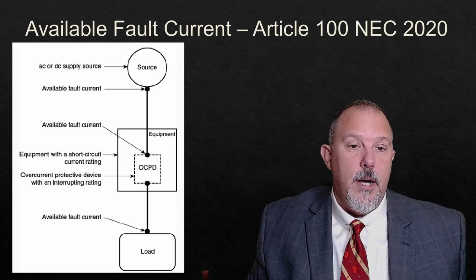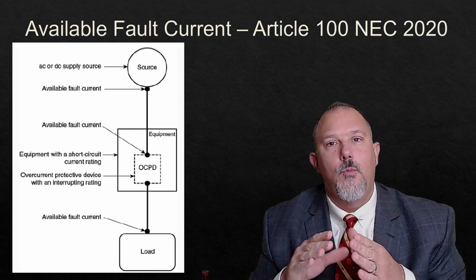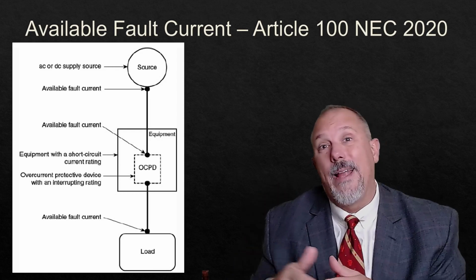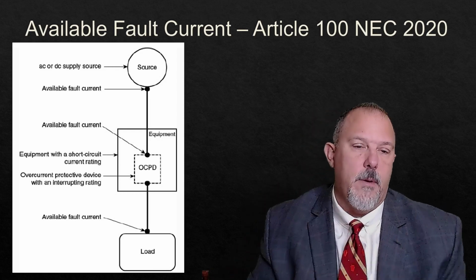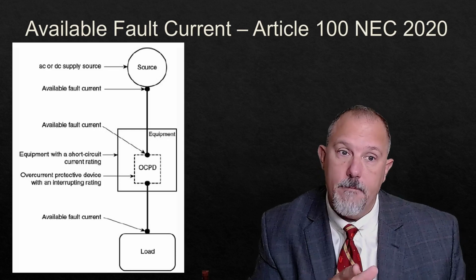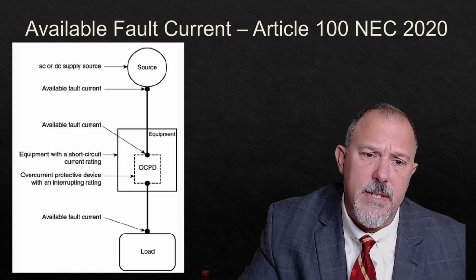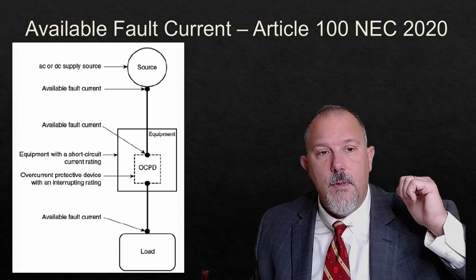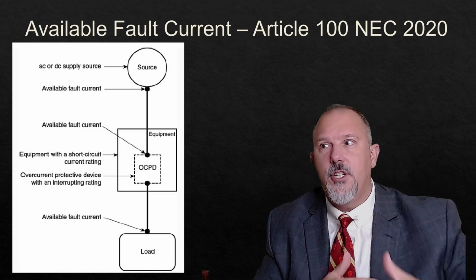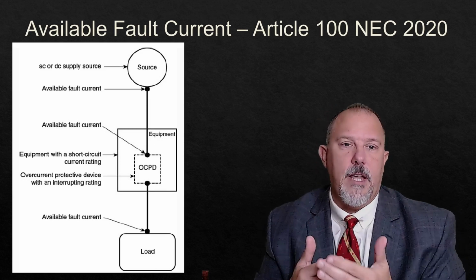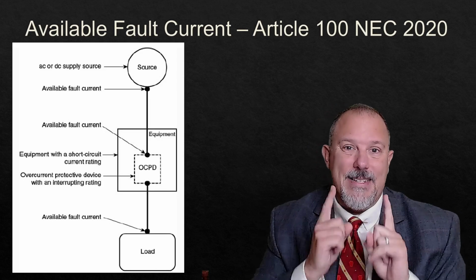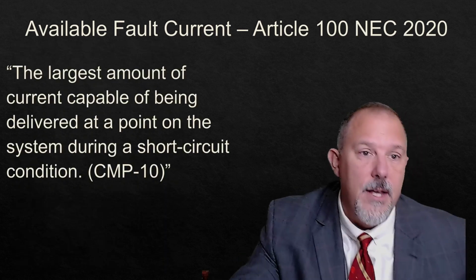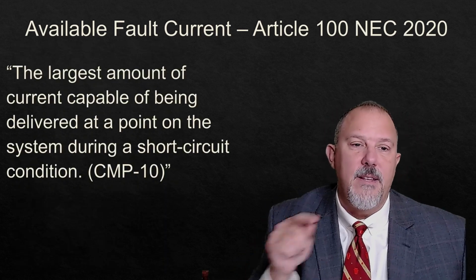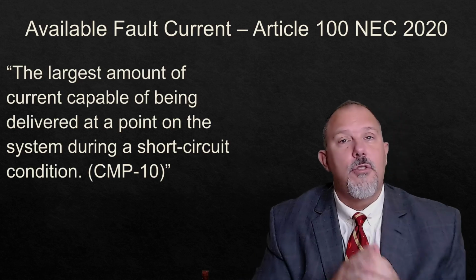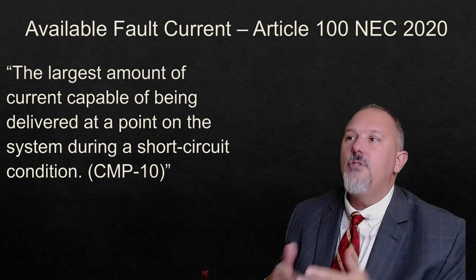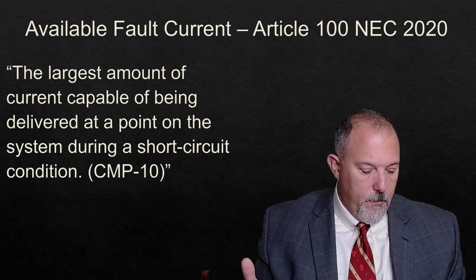So why do we do that? Because you want the maximum available fault current. You don't want to go downstream. You want to be at that equipment, and that will tell you the interrupting rating. Short circuit current rating is very similar. So the changes in the 2020 cycle were basically looking at, they wanted to create a term. Now remember what the definition says: the largest amount of current capable of being delivered. So we know it's the largest amount. So throughout the National Electrical Code, we used to say, you know what?